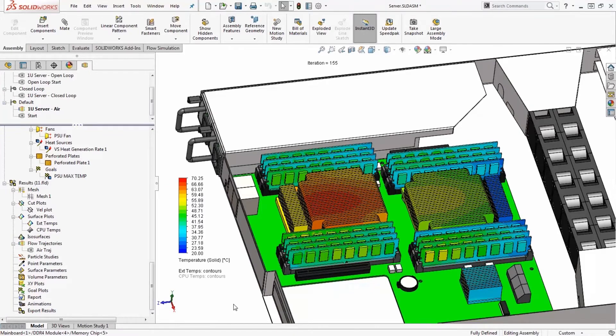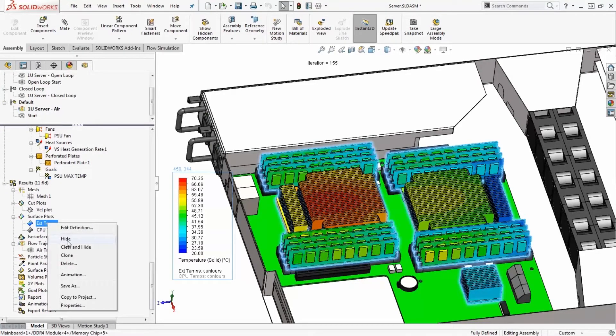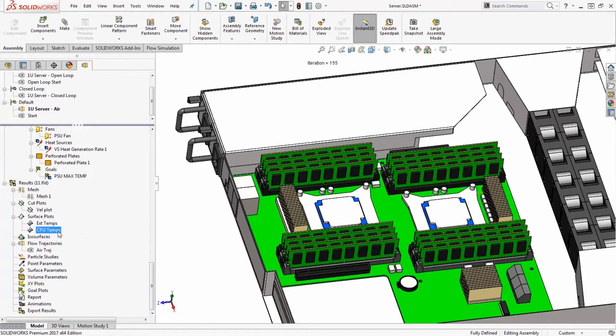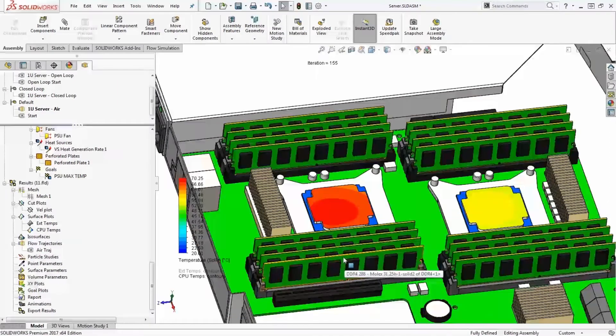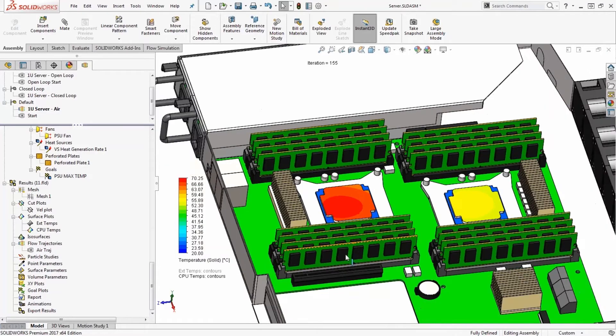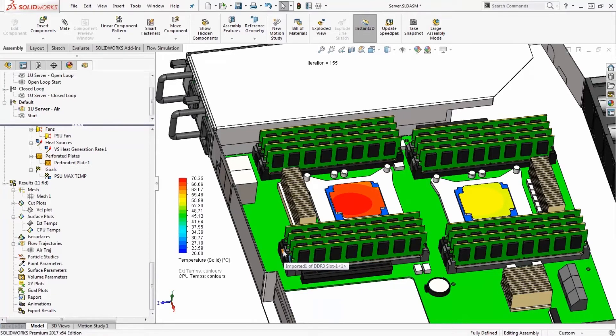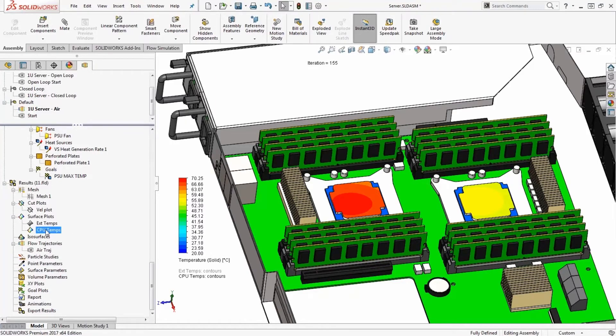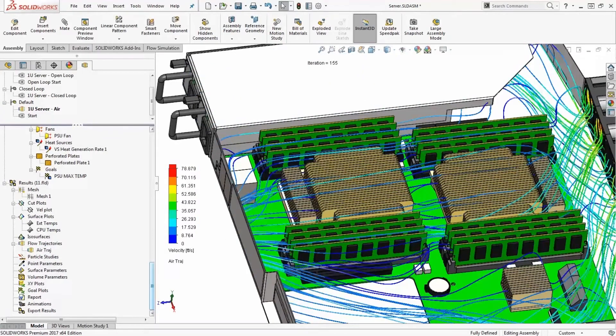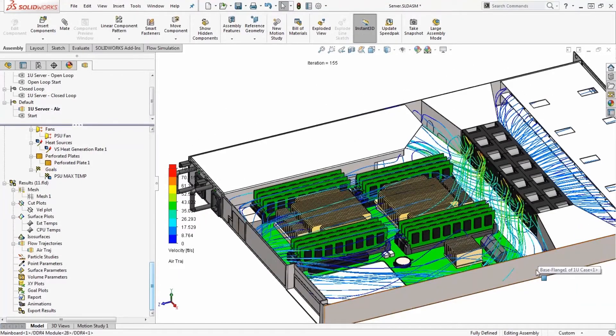There's really not much we can do with air cooling to improve the second CPU temperature unless we could put the two CPUs side by side. If we want to see the temperature of the actual chips, I can hide the heat sinks and do a surface plot on the chip tops to see the temperature distribution. These models are a little simplified — the simplification is optional, and one of the great things about Flow Simulation is we can run studies with basically no simplification, it just takes longer to solve. Flow trajectories are also a great way to visually identify bottlenecks or where fan placement could be improved.